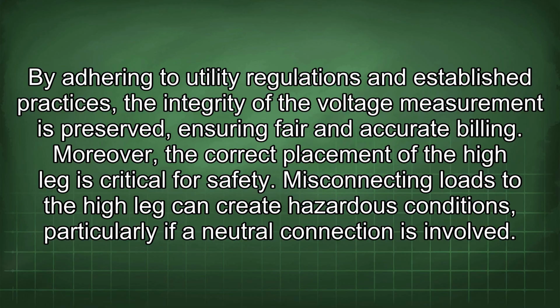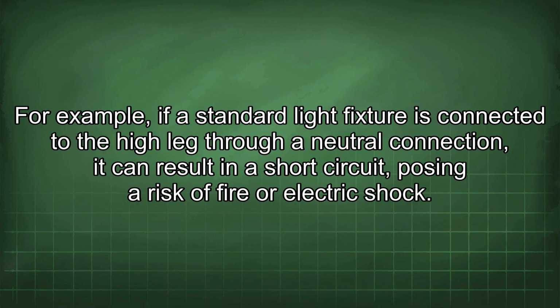Misconnecting loads to the high leg can create hazardous conditions, particularly if a neutral connection is involved. For example, if a standard light fixture is connected to the high leg through a neutral connection, it can result in a short circuit, posing a risk of fire or electric shock.